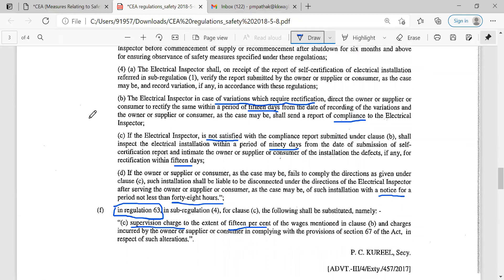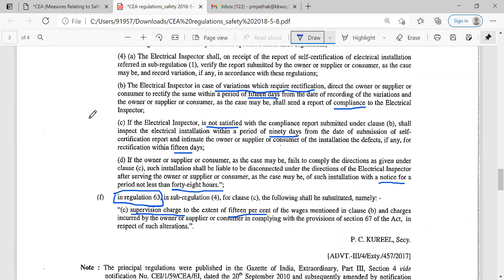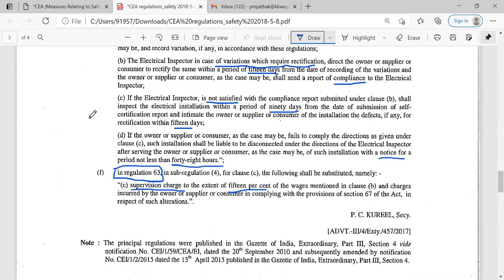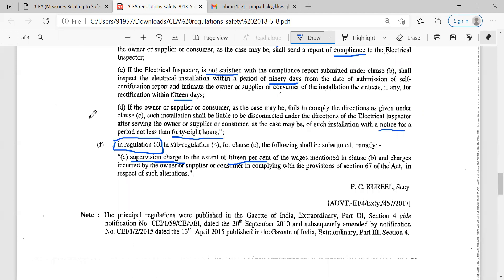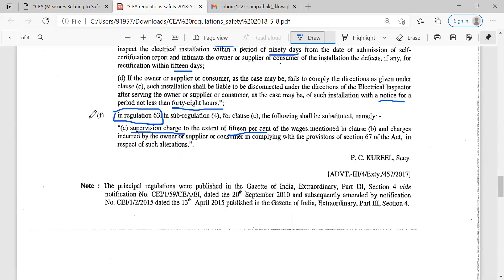That is the same provision given in regulation 30, and again the same provisions apply for regulation 43 also — similar to the authority provisions. If any variation is found by that electrical inspector, that requires rectifications, and within a period of 15 days they have to comply with all these things. If it is not complied or if the electrical inspector is not satisfied with the compliance given by the owner or consumer, then within the 90 days period of submission or exceeding that period within 15 days, he may give notice to the owner or the consumer. If he feels that disconnection is the proper step, then he can go ahead with the disconnection process.